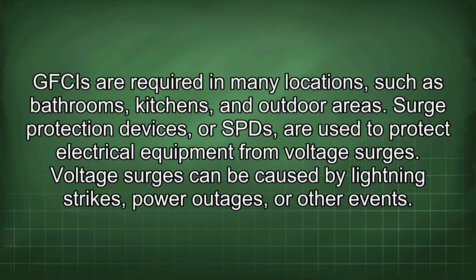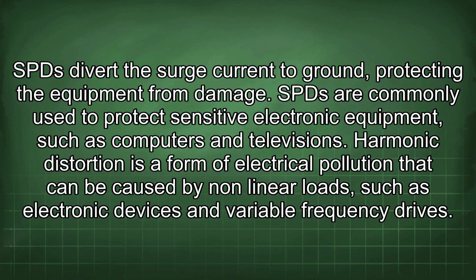Surge protection devices, or SPDs, are used to protect electrical equipment from voltage surges. Voltage surges can be caused by lightning strikes, power outages, or other events. SPDs divert the surge current to ground, protecting the equipment from damage. SPDs are commonly used to protect sensitive electronic equipment, such as computers and televisions.